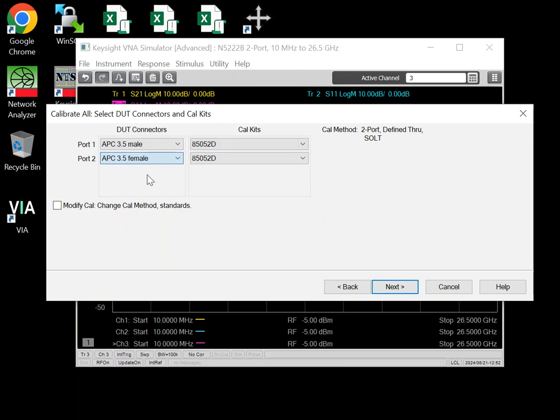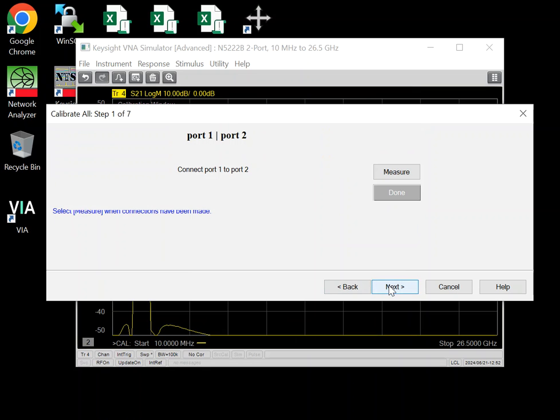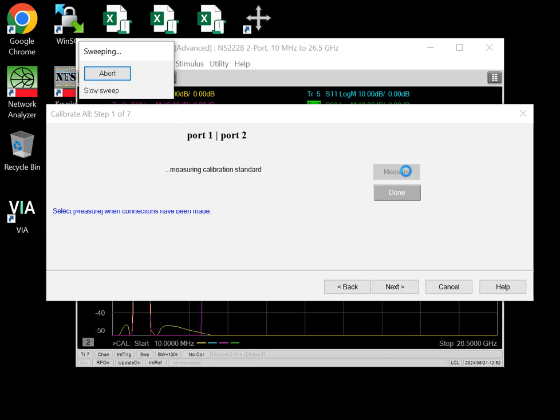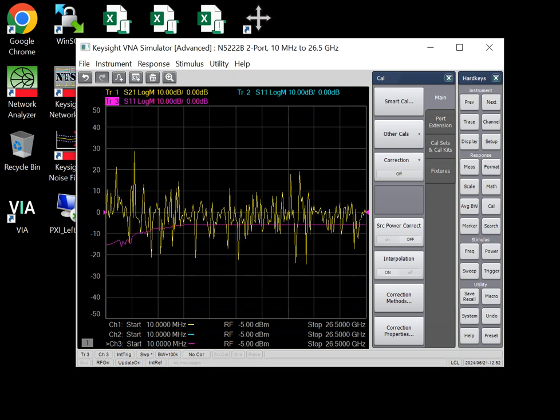And let me go back to the 85052D here. Make it male, female. So it now calibrates all these three channels once. You don't have to connect the standards multiple times. So that's what Cal all's benefit is. And that's it.